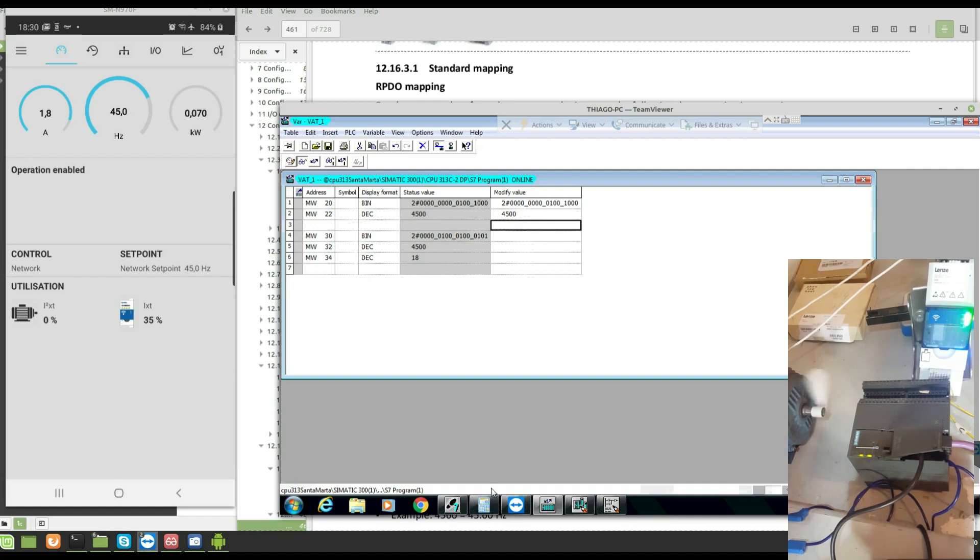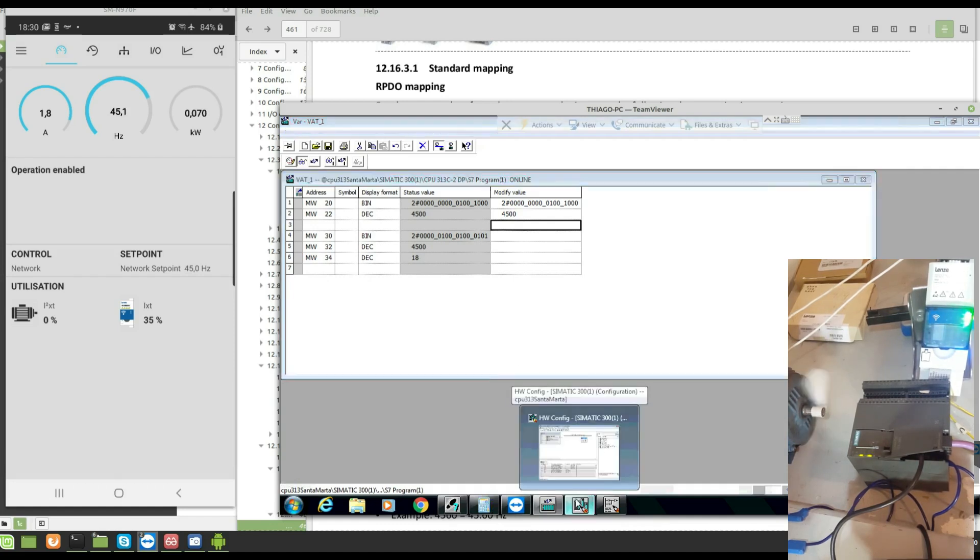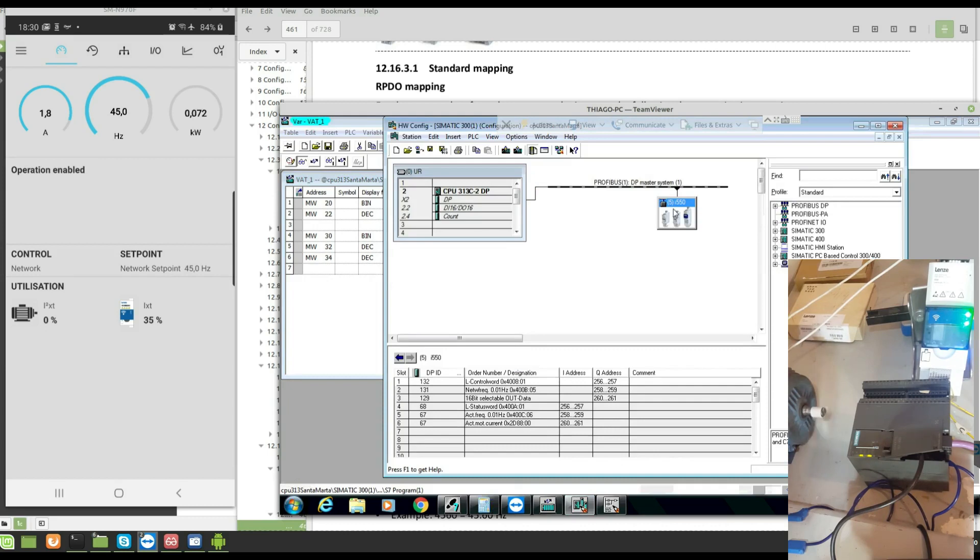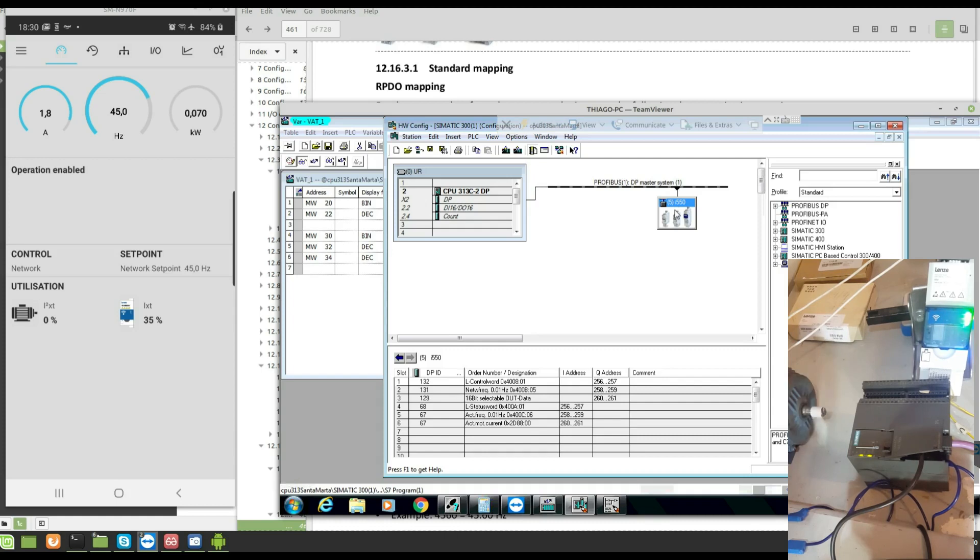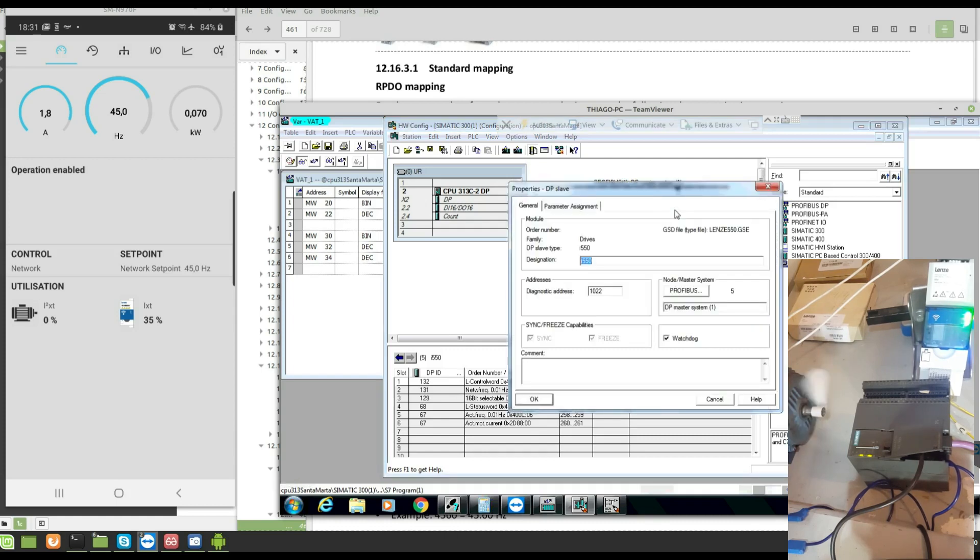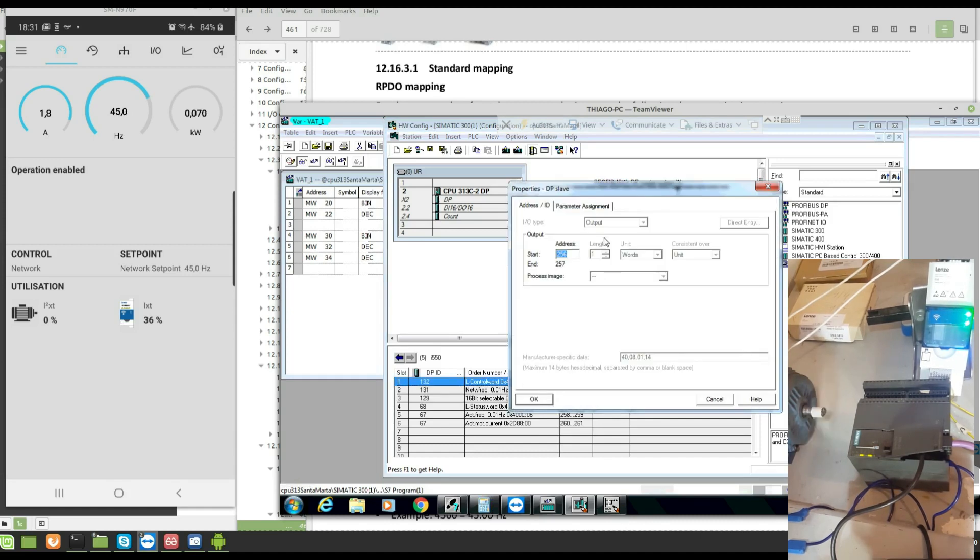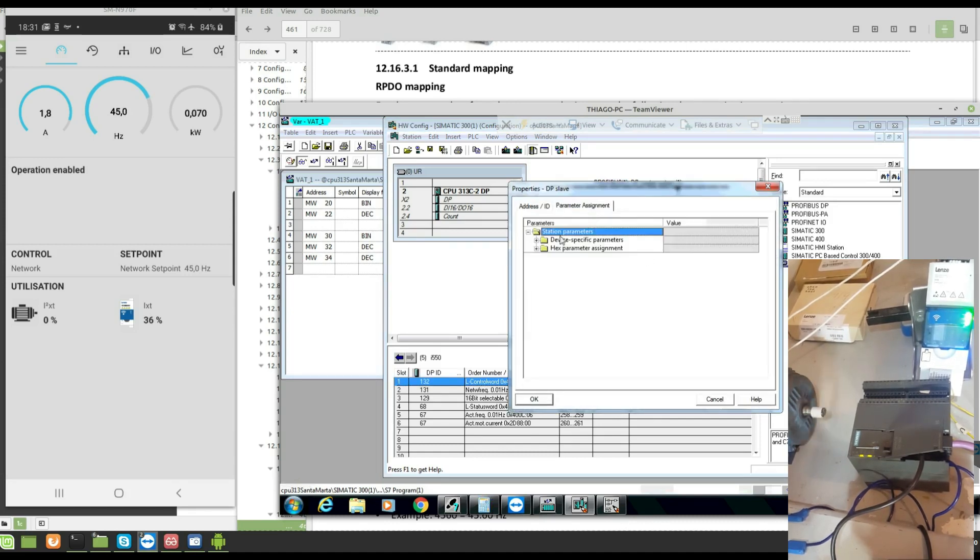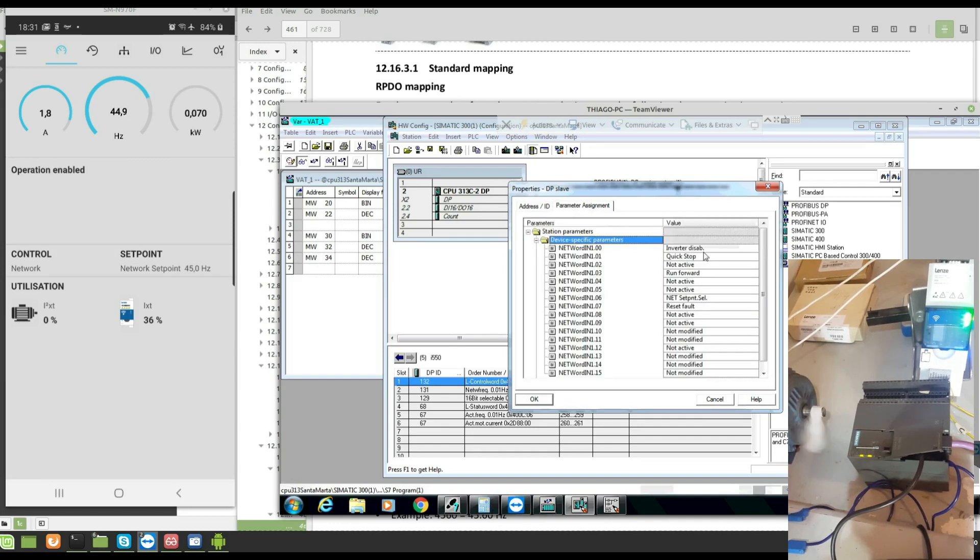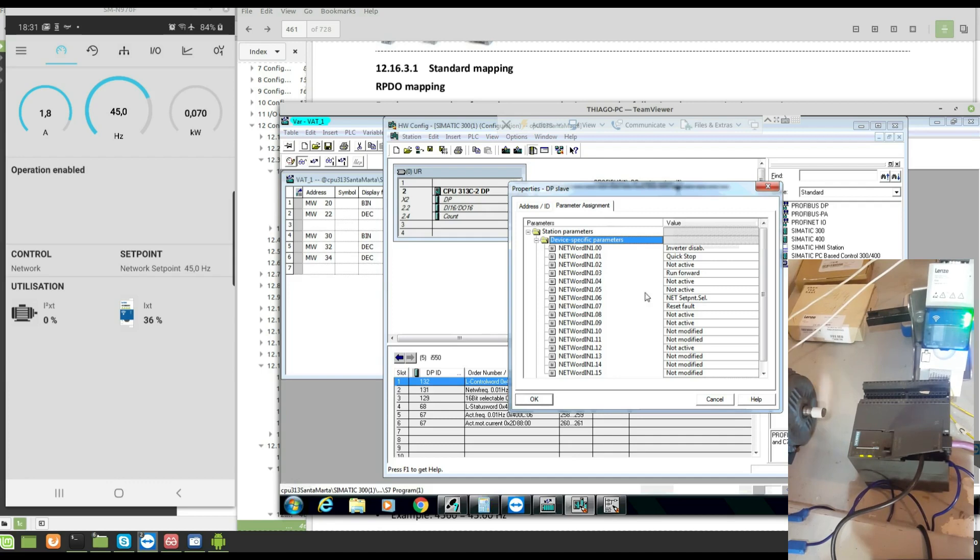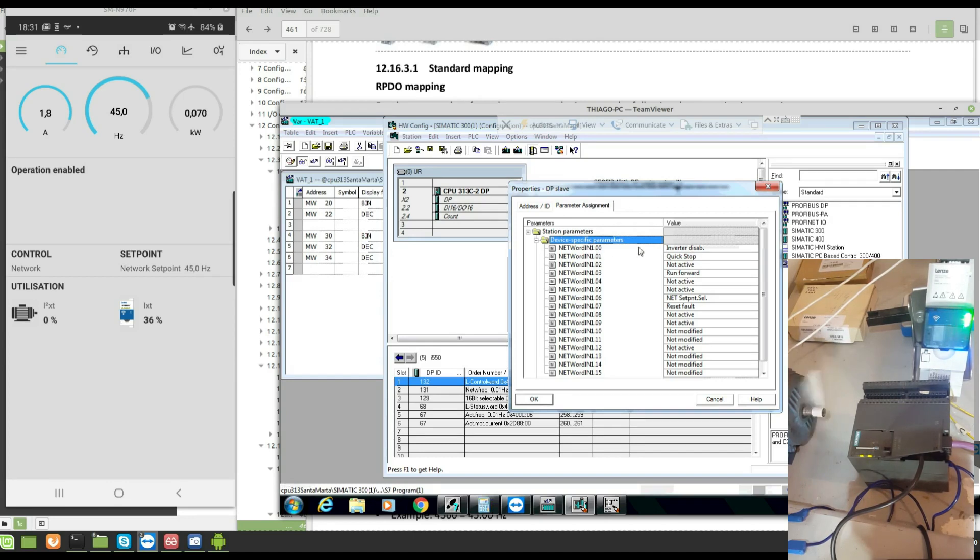For the last thing that I'm going to show you is the importance when you change the parameters in the control words, you must ensure that you change it here too, the parameter segments. Take a look, the device parameter segment. Look, I changed it. Run forward now is in bit three, quick stop in bit one, bit zero to disable the inverter.